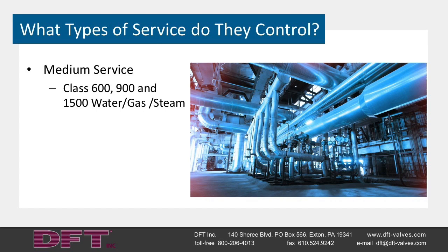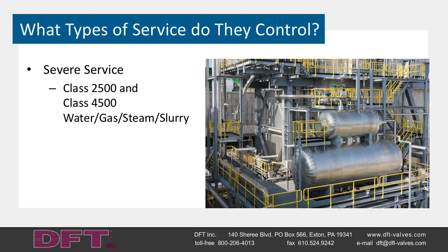Medium service includes class 600, 900, and 1500 in water, gas, and steam service. An example of medium service would be 1,000 PSIG general service steam in refinery, chemical, or pulp and paper plants. Severe service includes class 2,500 and 4,500, water, gas, steam, or slurry service. An example of severe service would be boiler feed water with an inlet pressure of 2,650 PSIG and a pressure drop of 2,580 PSIG. DFT produces specific products for all three types of service. Today we are here to discuss our most challenging of these: severe service.